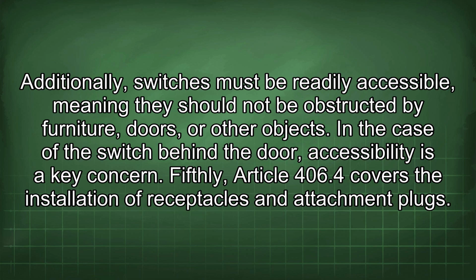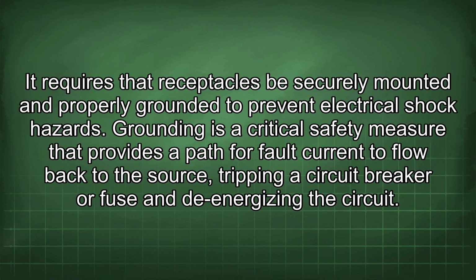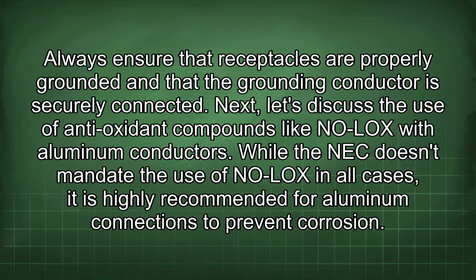Fifthly, Article 406.4 covers the installation of receptacles and attachment plugs. It requires that receptacles be securely mounted and properly grounded to prevent electrical shock hazards. Grounding is a critical safety measure that provides a path for fault current to flow back to the source, tripping a circuit breaker or fuse and de-energizing the circuit. Always ensure that receptacles are properly grounded and that the grounding conductor is securely connected.